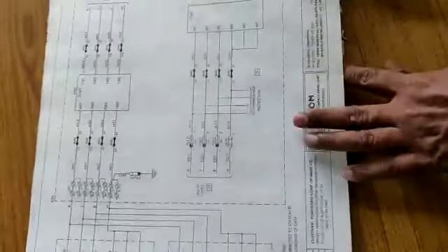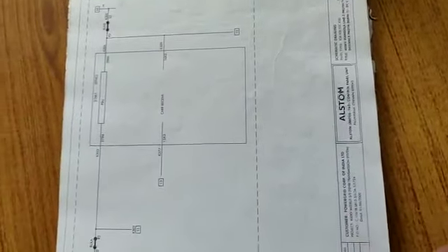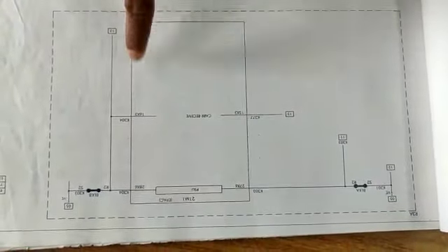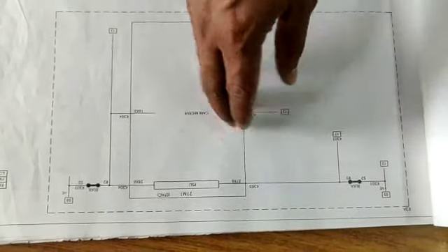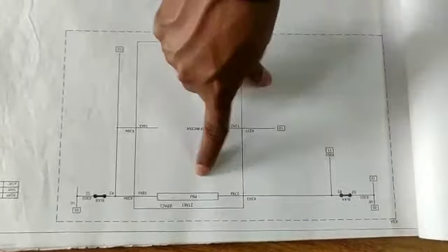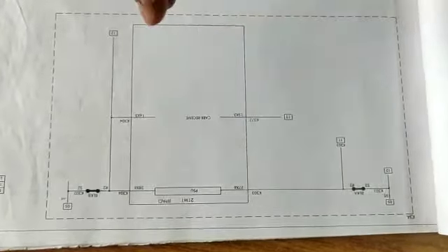Now after these two, we will refer to the next page, and in the next page, if you look at this block or this rectangle, it generally shows a relay or numerical relay. So from here the main scheme drawing starts. In this, the PSU, if it is mentioned, sometimes it is not mentioned in some scheme drawings, but if it is mentioned, it simply means power supply unit, and you know that any relay will have to be powered on through a 220 volt DC source.